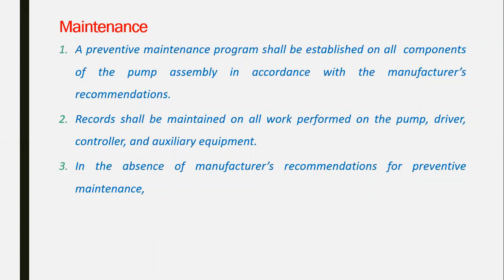The preventive maintenance program is mainly based on the manufacturer recommendation: the intervals for the preventive maintenance, what the spare parts will be, what the tests will be as preventive maintenance, and the replacement of devices, depending on the manufacturer recommendation. NFPA doesn't have any recommendation itself. They have proposals for a recommendation, which I will show you, but it is not restricted. They keep it depending on the manufacturer recommendation as well.